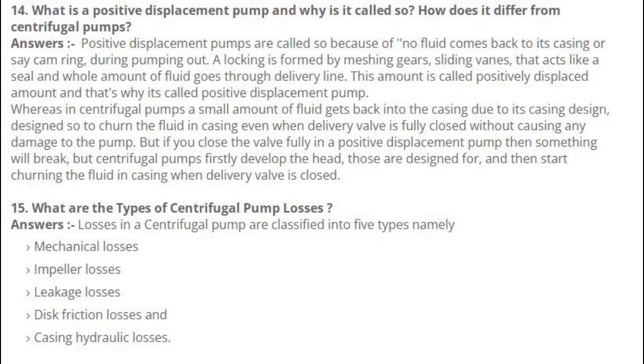Number 14: What is a positive displacement pump and why is it called so? How does it differ from centrifugal pumps? Positive displacement pumps are called so because no fluid comes back to the casing or cam ring during pumping out. A locking is formed by meshing gears and sliding vanes that act like a seal, and the whole amount of fluid goes through the delivery line — this amount is called the positively displaced amount. In centrifugal pumps, a small amount of fluid gets back into the casing due to its casing design, allowing the pump to churn fluid even when the delivery valve is fully closed without damage. But if you close the valve fully in a positive displacement pump, something will break.